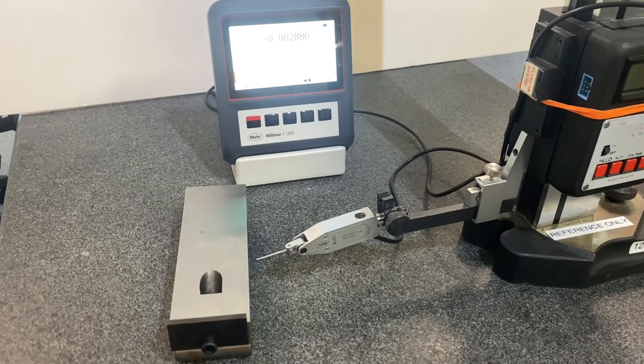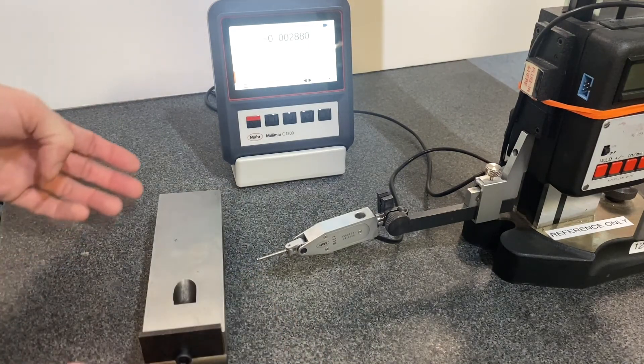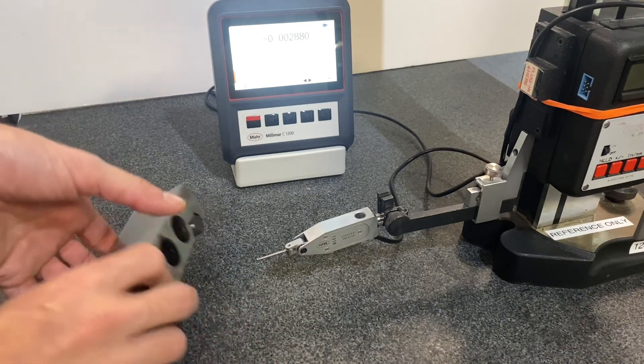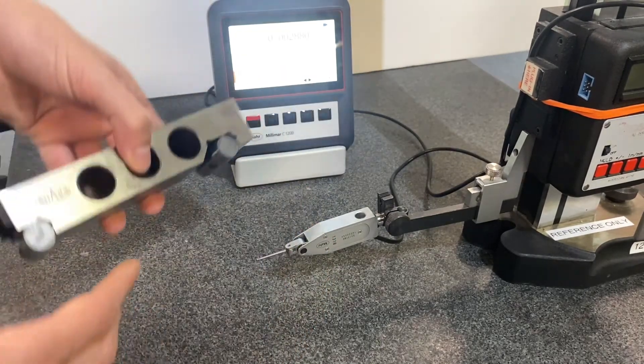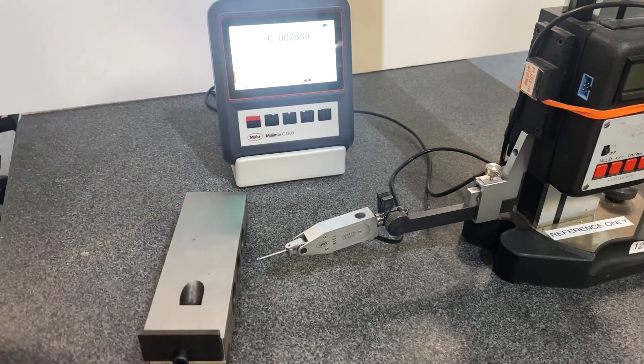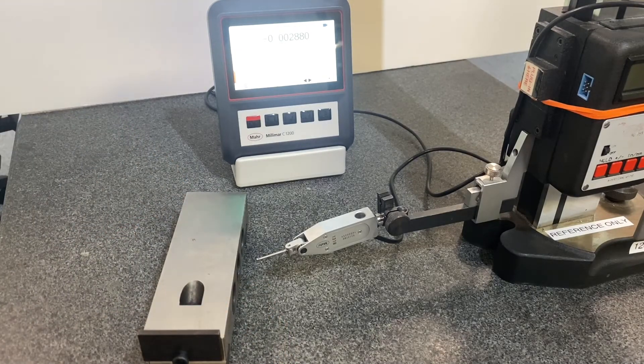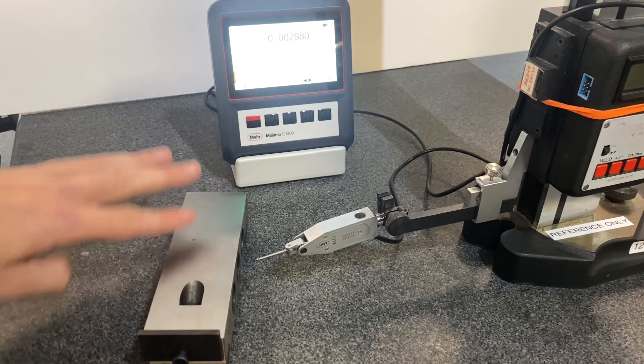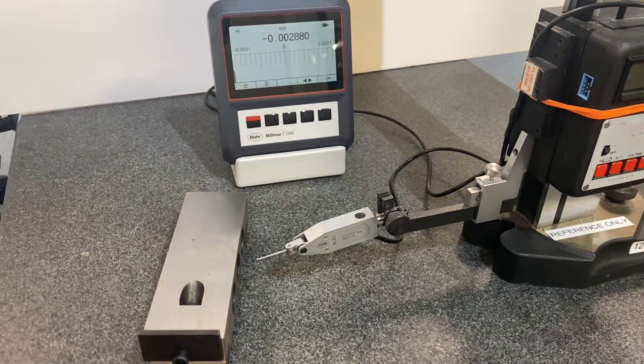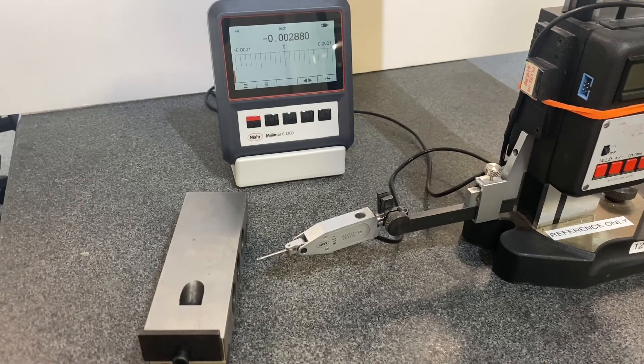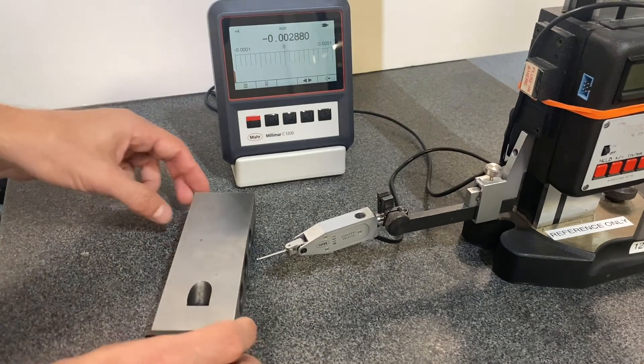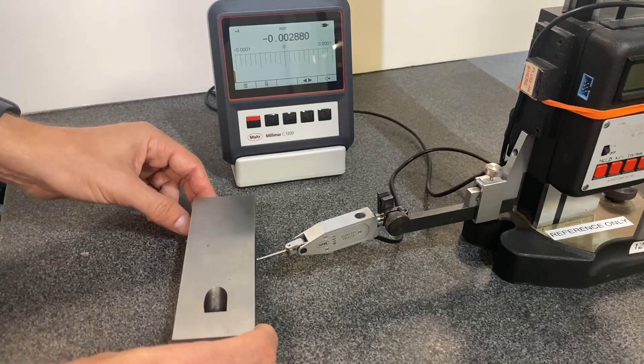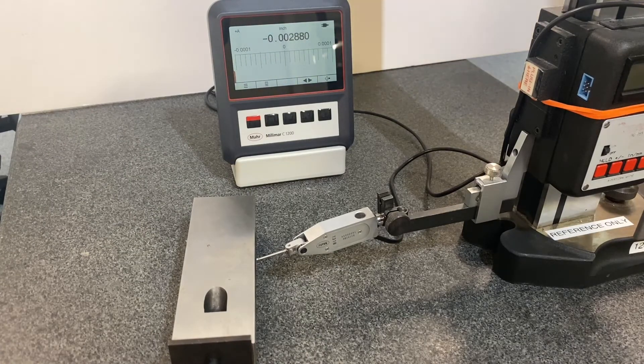In this video we will be doing part two of how to calibrate the sine bar. In the first section we used the vision system to measure the distance between the pins and the diameter of the pins. In this section we will be measuring the TIR, the total indicated range of the surface of the sine bar using the inductive probe and this surface plate. I've already positioned the probe to be just above the surface and we're going to measure the TIR.